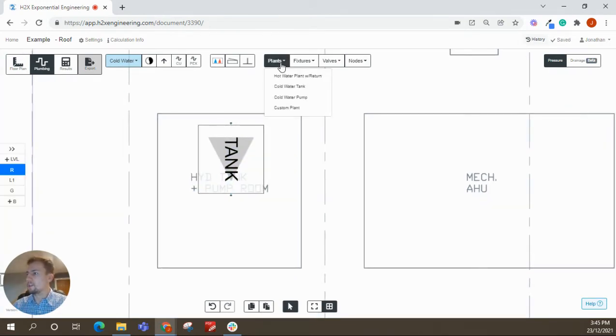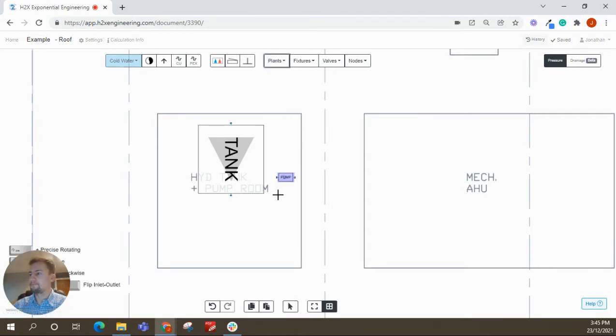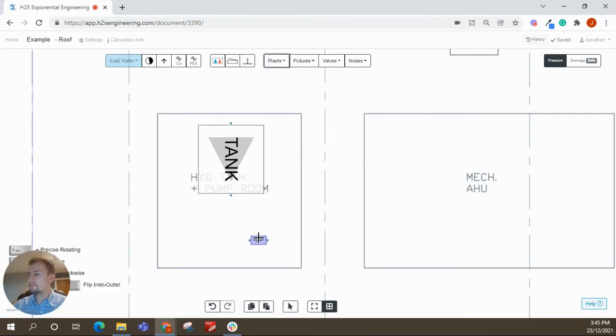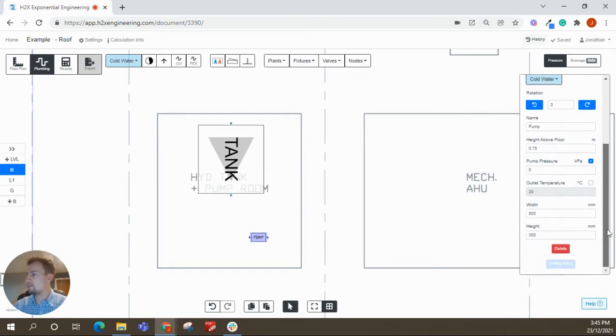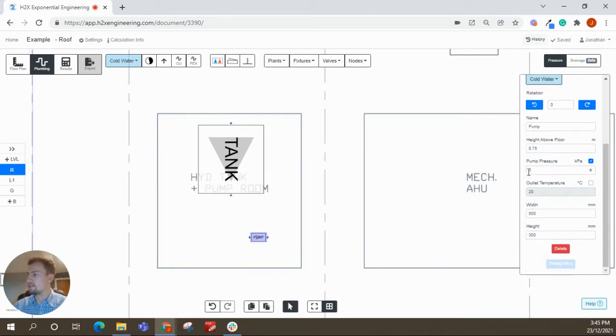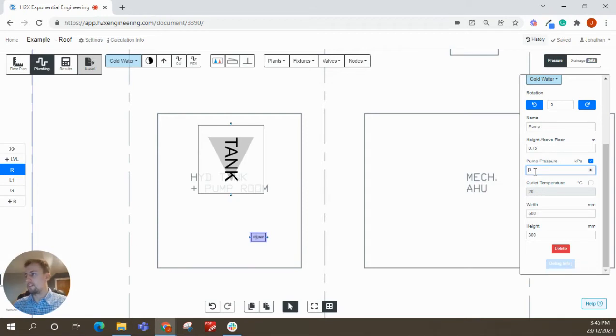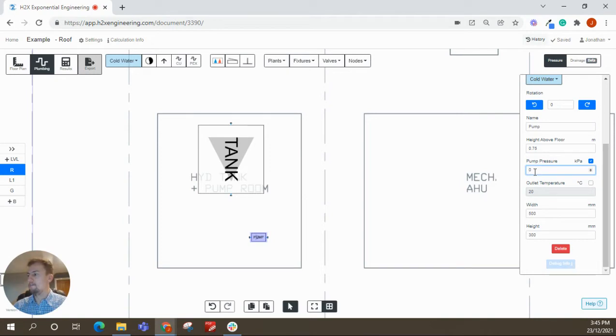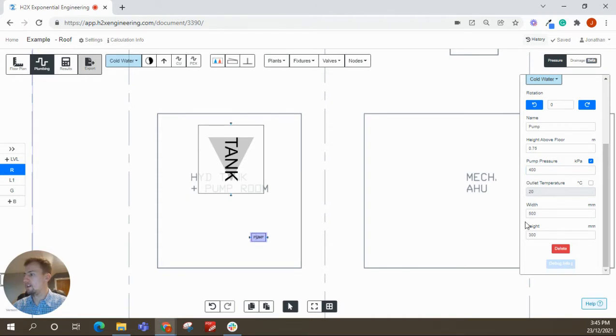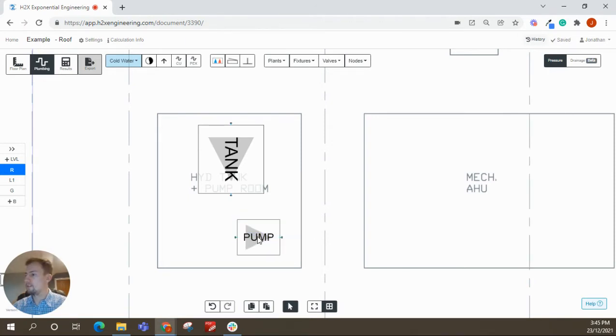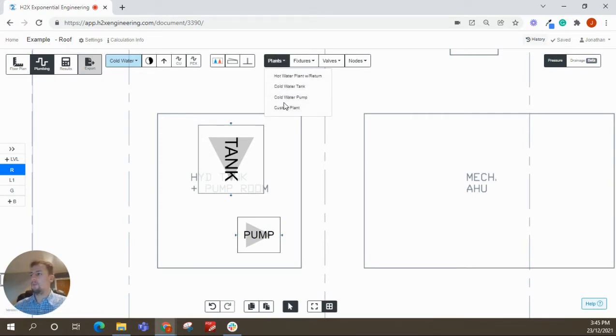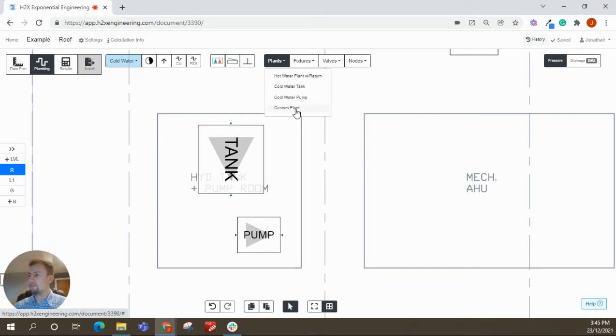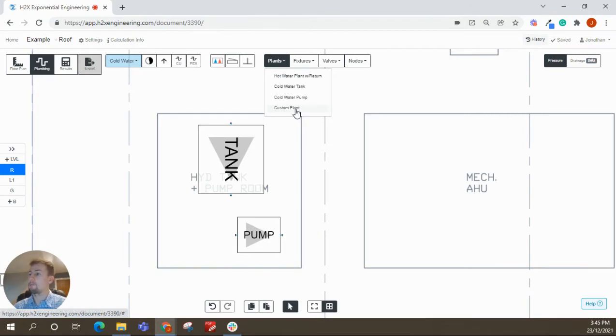All right. And because we've got a tank, we'll then need a pump. So exactly the same. Very similar settings. The main one here is the pump pressure. So I usually just leave that at zero. When we've got the results, see how little pressure we have on the fixtures and come back and change it. But you can also just put a placeholder in as well. So maybe like 400 KPA and just change it as well. And then if you have anything like filters, water softener or anything like that, you can also create your own custom plant, which I won't need here, but give it a name, enter some pressure loss, tell it what pipes you want to connect to it. And yeah, you can pretty much make anything that you want to with that.